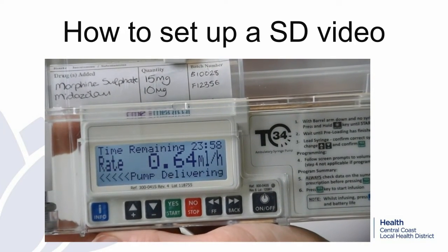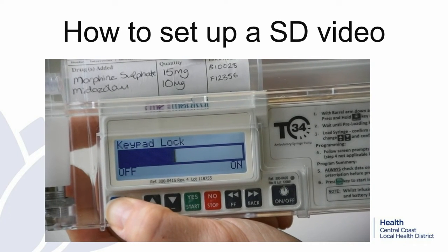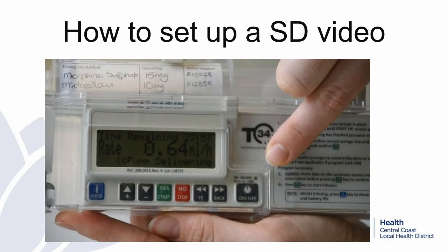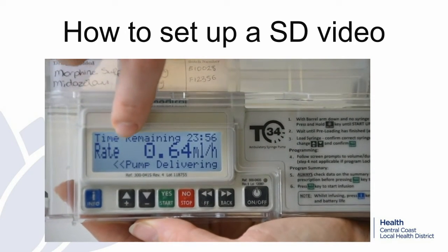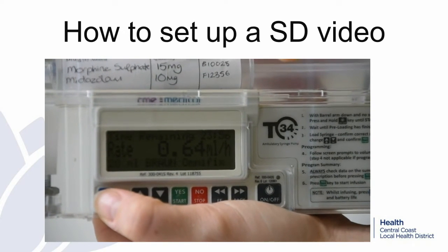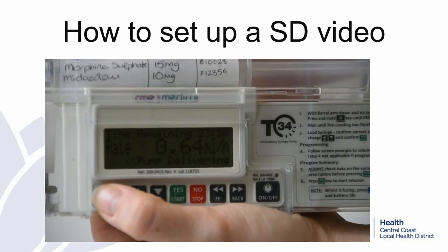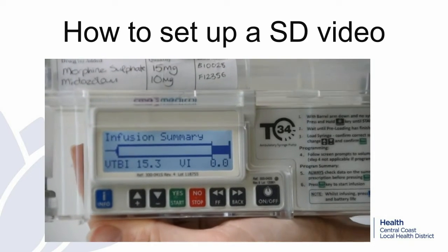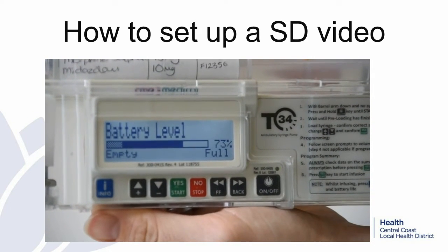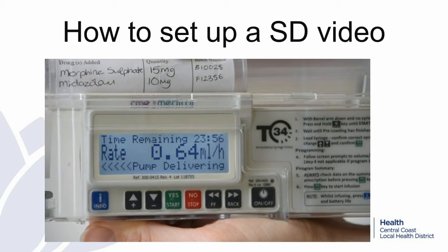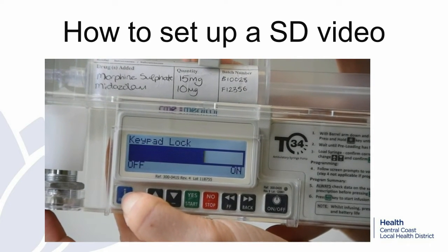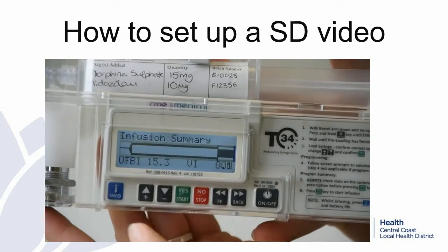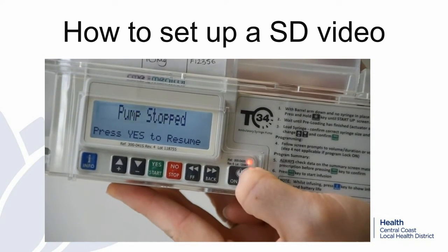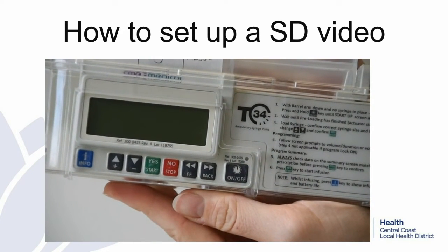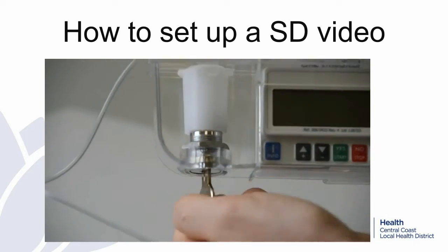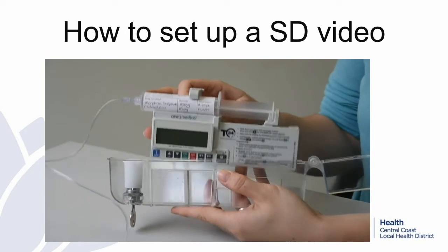To lock the keypad, press and hold the info button until it beeps. Ensure the green light flashes and the main screen says pump delivering. For 4 hourly checks, you will find the infusion rate and time remaining on the main screen. And to check the battery level and volume remaining and volume infused, press the info button twice. Unlock the keypad by pressing and holding down the info button and wait for the beep. Press the stop key, press and hold the on and off button. Disconnect the syringe from the line, then remove the syringe from the pump, and you are ready to start again with all of the checks from the beginning.